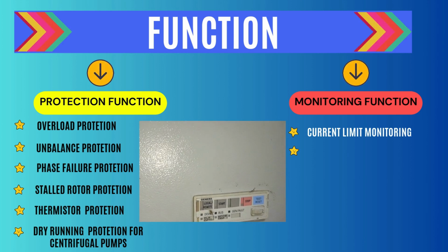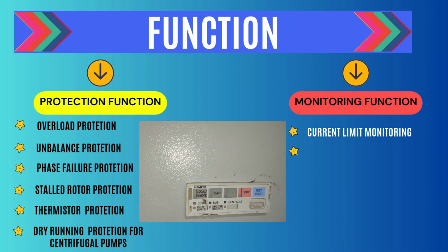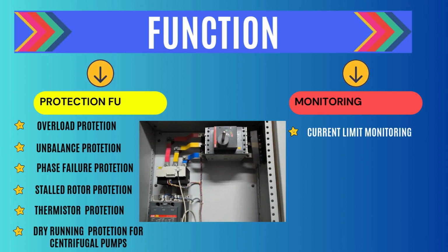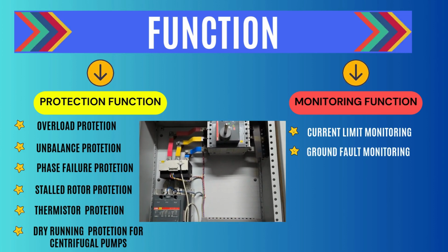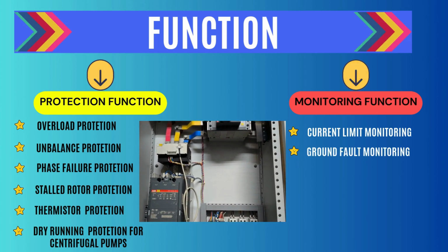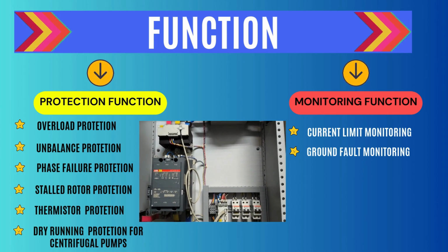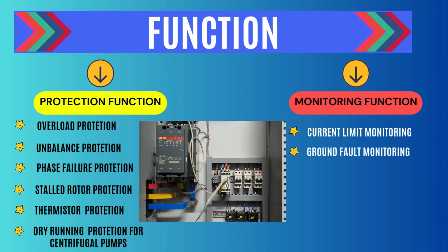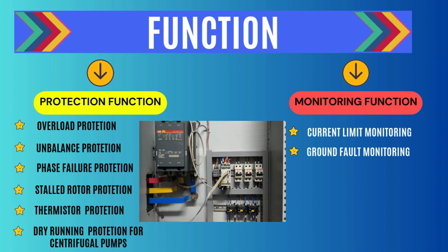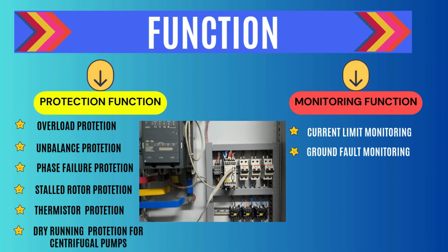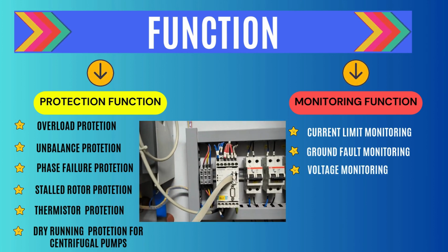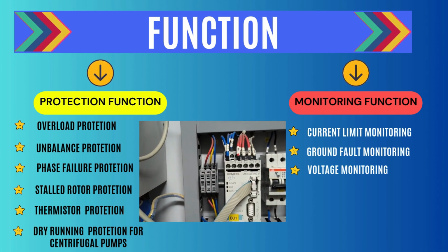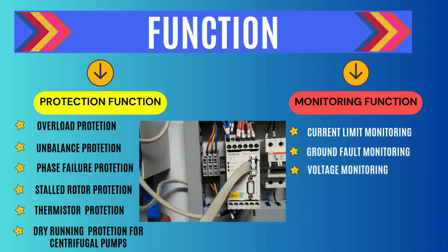Ground fault monitoring. Residual current monitoring relays are used in industry to protect systems from damage caused by residual current, prevent production losses caused by unplanned downtime, and perform maintenance to meet all demands. Voltage monitoring. Monitor for undervoltage, monitor for further availability. Even when the motor is switched off, Simocode Pro can indicate the availability of the feeder by measuring the voltage directly at the circuit breaker or fuses.